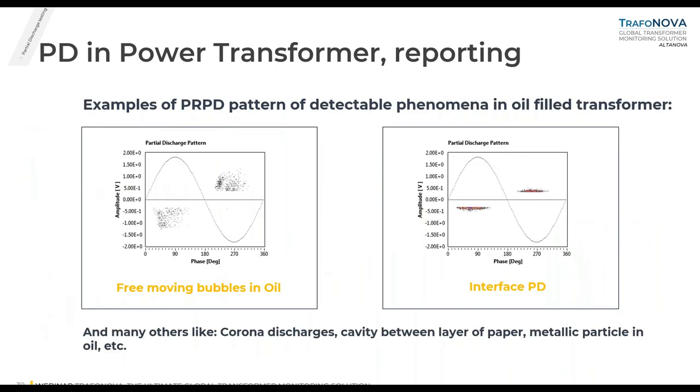Regarding typical PRPD patterns, I'd like to share two: on the left, partial discharge in oil bubbles; on the right, interface PD — typical PD occurring at the interface of two different materials with different electric strength. There are many other defect types identifiable with the system: corona discharges, cavities between layers of paper, and metallic particles in oil.